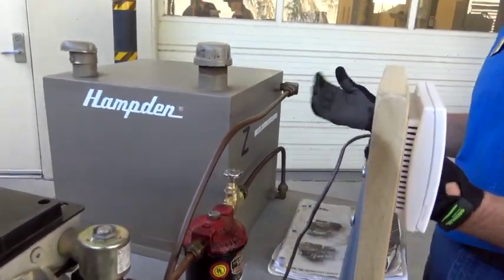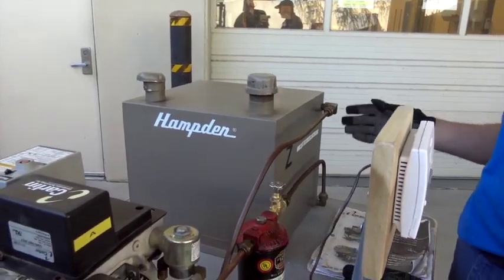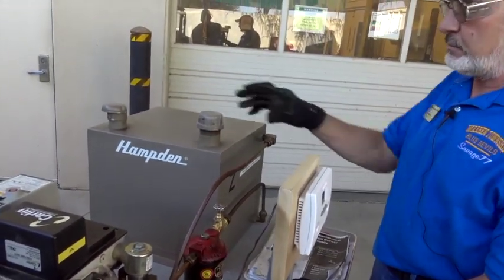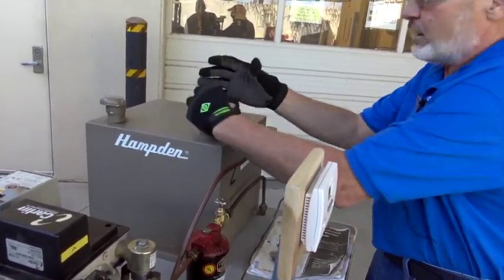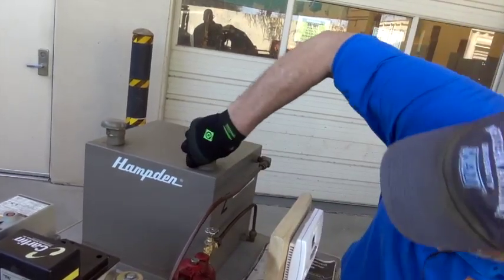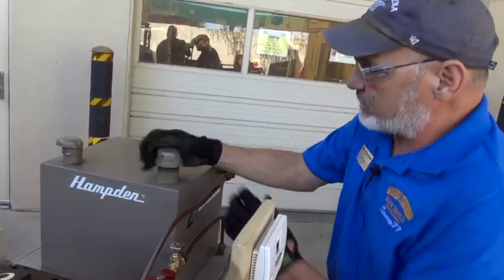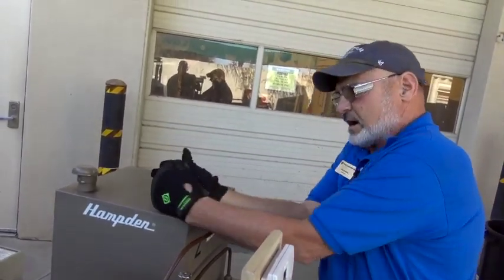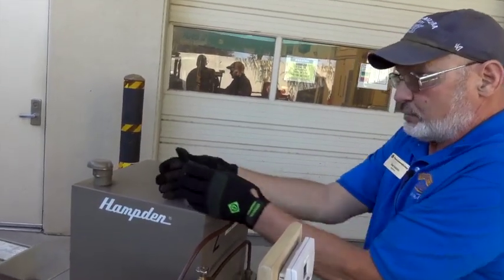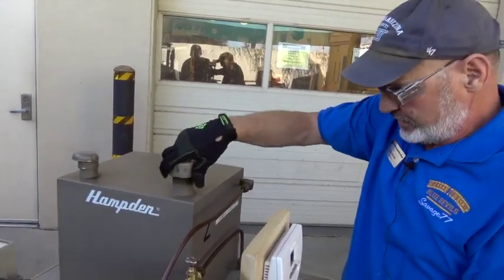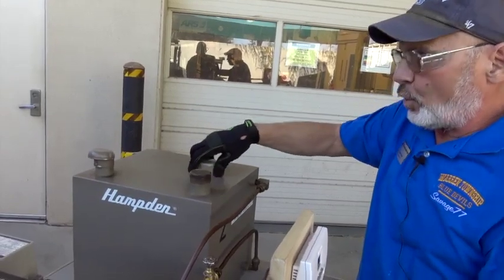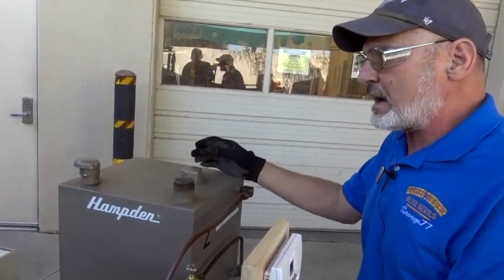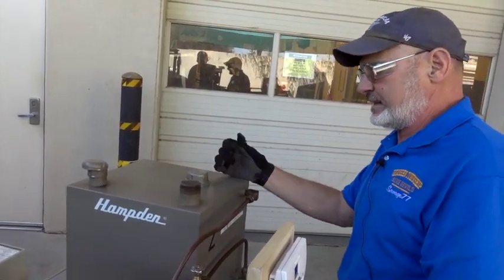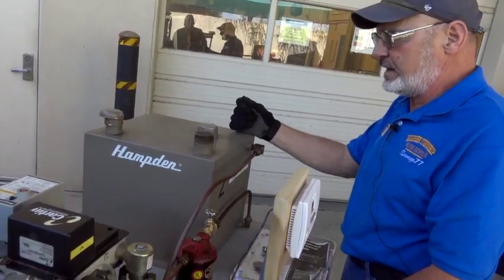Normally this is a simulated tank, how a tank would be. Most fuel tanks are big and they're outside. Now somebody put a big cap on here, it's supposed to be just real hand tight. We want to make sure it's tight. We don't want no moisture to get in there. But we also got to worry about electrostatic discharge. I don't think it's a big deal out here, but it could be.